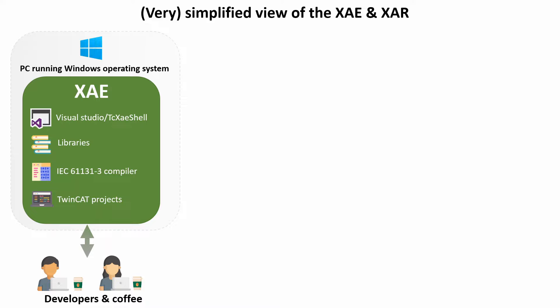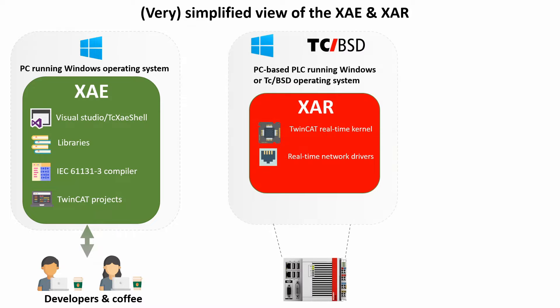The XAE is always installed on a Windows machine, so you can't run this on any other operating system such as Linux. Next, we have the XAR, which stands for Extended Automation Runtime. In here we find the TwinCAT real-time kernel, which provides the deterministic properties of our PLC software. We also find drivers for the industrial fieldbus protocols, such as EtherCAT. The XAR can be installed both on a Windows machine and Beckhoff's own operating system TC-BSD.